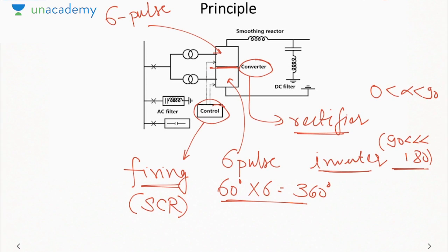So here bidirectional power flow is easier as compared to AC, because in AC we studied power flows from higher angle to lower angle. So we actually had to change the power angle. But here we just have to change the firing angle, which can easily be done by means of this control circuit. Now the output of the converter is pulsating DC. So we have to smoothen it out, hence we use a smoothing reactor to smoothen out the voltage waveform at the DC terminals of the converter.